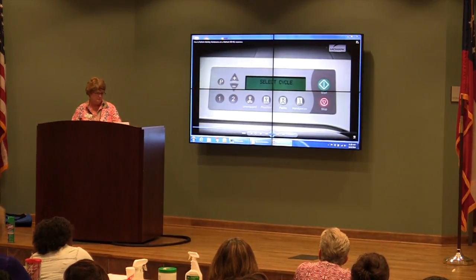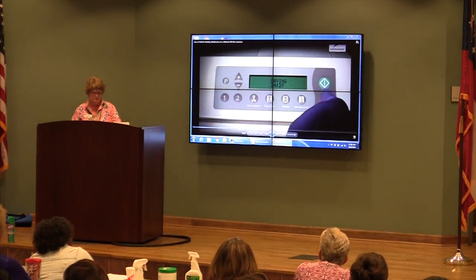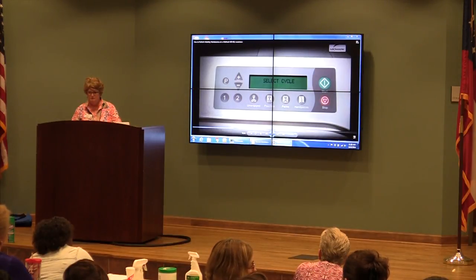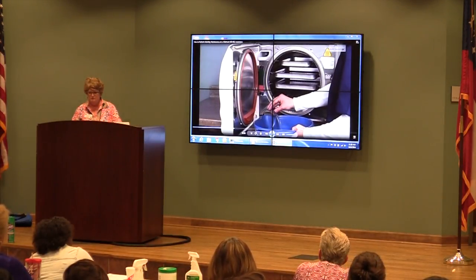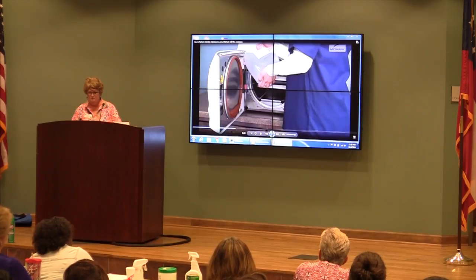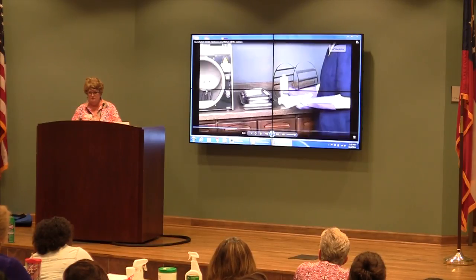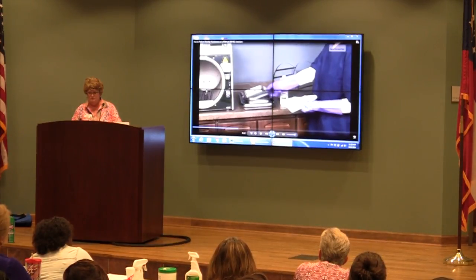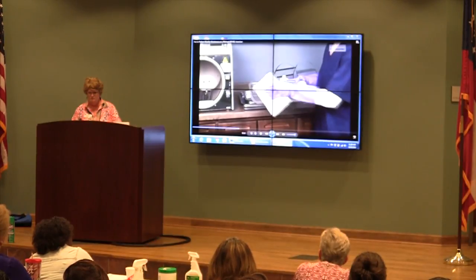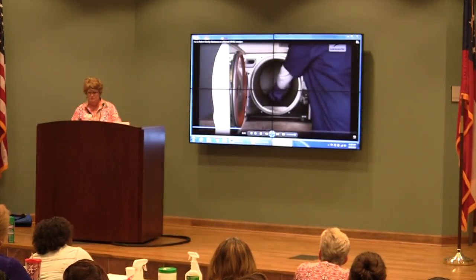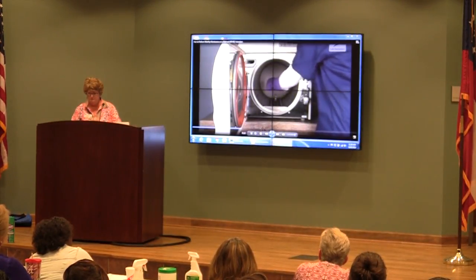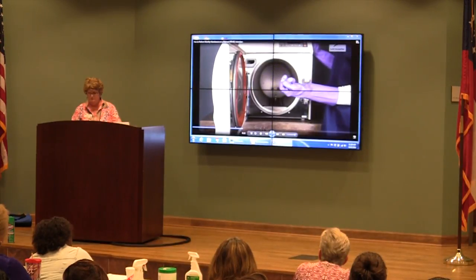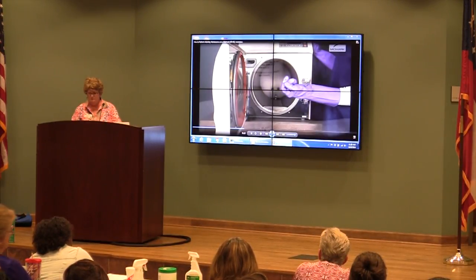Rinse by running 1 unwrapped cycle. Push the stop button when the drying cycle begins. After the cycle has completed, drain and fill the reservoir with clean distilled water, then allow the sterilizer to cool. Remove the trays and tray rack and wipe with a damp cloth. Next, remove and clean filters. Remove filters by pulling upward and twisting slightly.